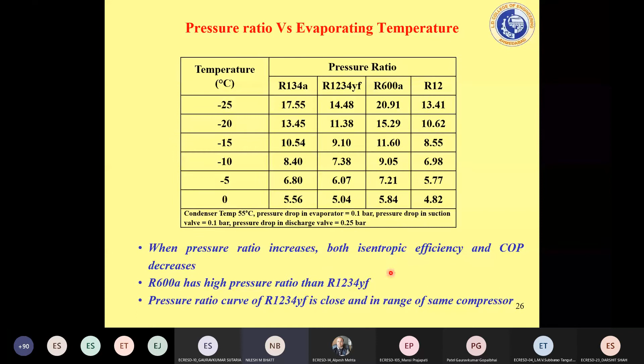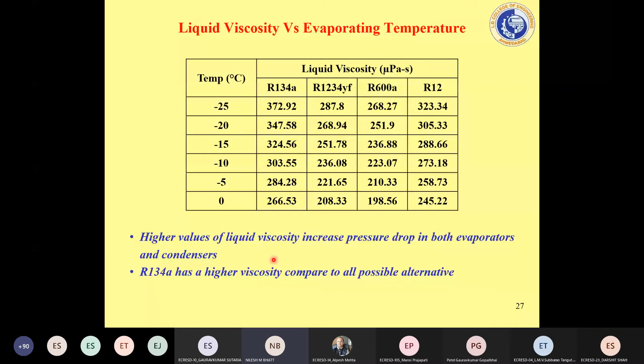The fact is that as pressure ratio increases, both isentropic efficiency and COP decrease. We can see that the pressure ratio for R600A is very high, and the pressure ratio curve for YF is close, in the range of the same compressor, to that of R134A. If we compare the liquid viscosity, the YF properties are very similar to R134A, and viscosity is very important as far as pressure drop is concerned. Now, looking at the time constraint, I will quickly give you the idea regarding the thermodynamic investigation. I'm not once again mentioning all these numbers directly; indirectly I mentioned them earlier.